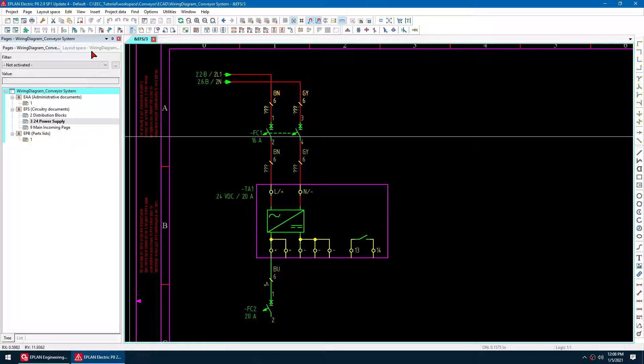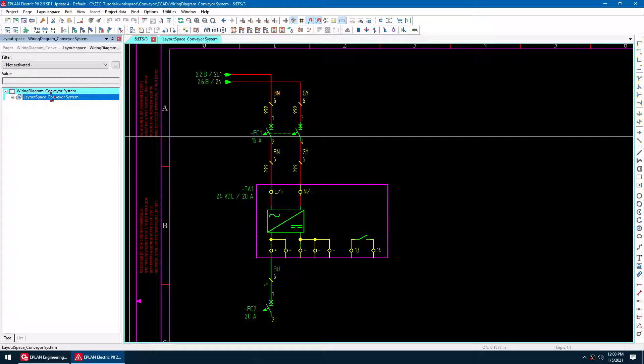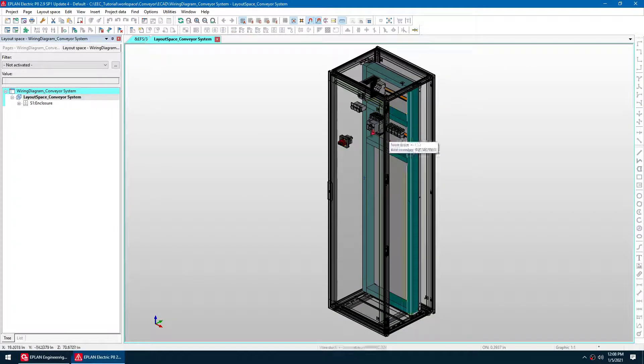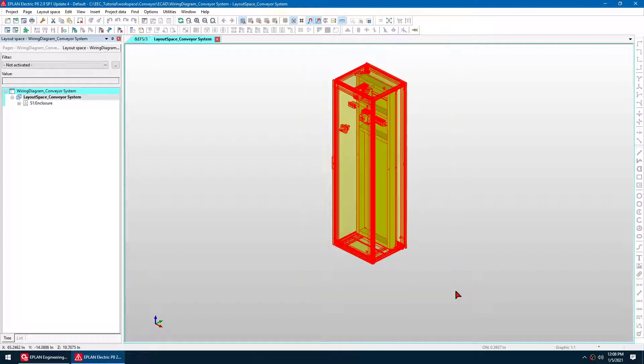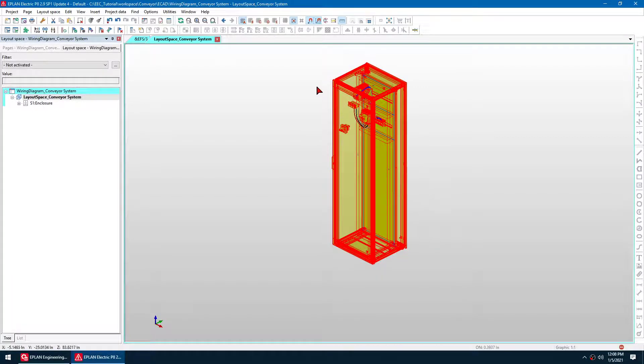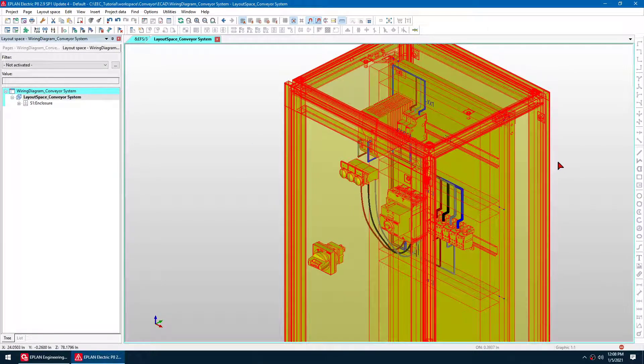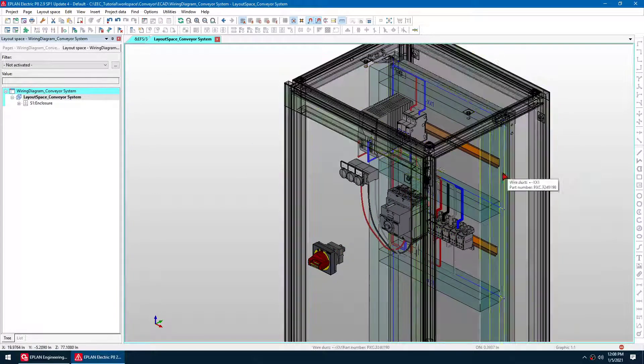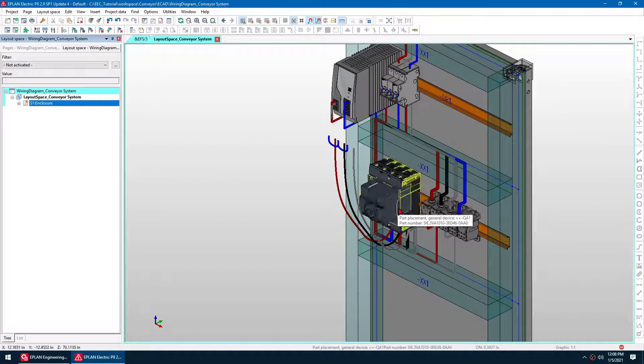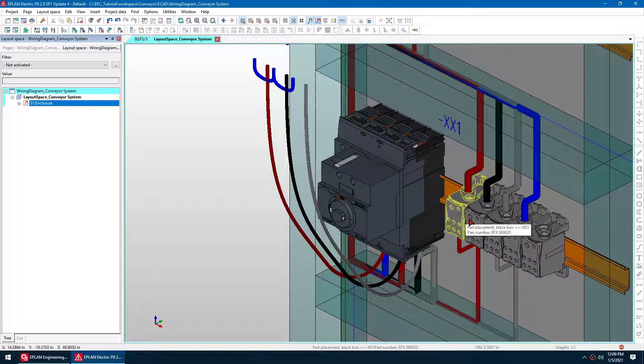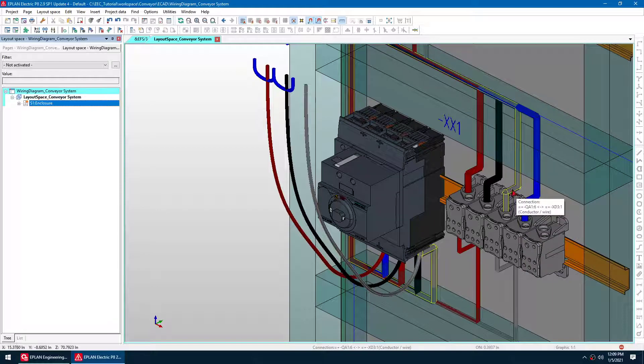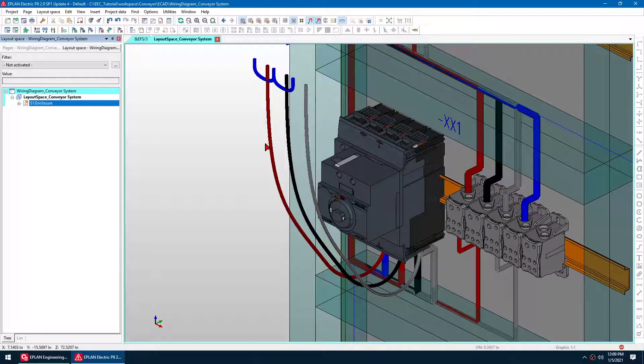So let's have a look at the 3D side of it, because this is also really interesting. So here's the cabinet and I can actually tell it to route. So first I'm going to route everything out the ducts and stick everything into the wiring ducts. And then we can actually have a look at the gauges of the wire here. If I just show only the mounting panel, we can see that this is the 100 amp version here. And I've got my distribution blocks, that large gauge wire.